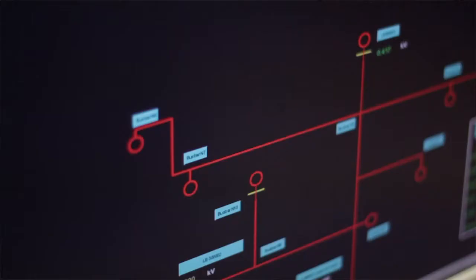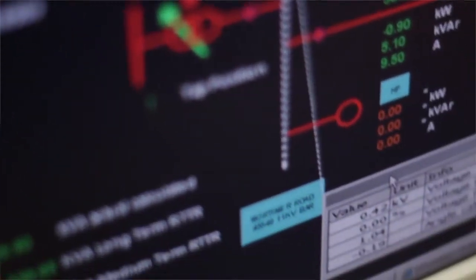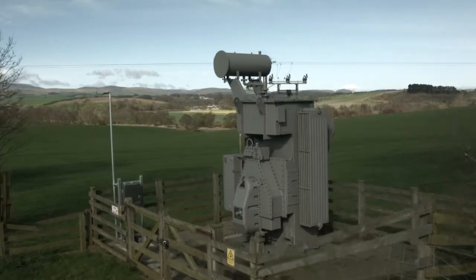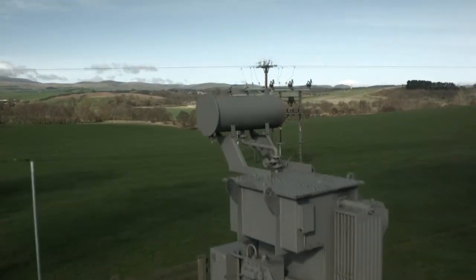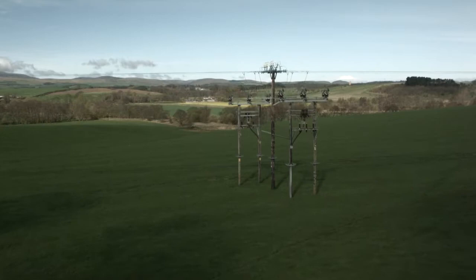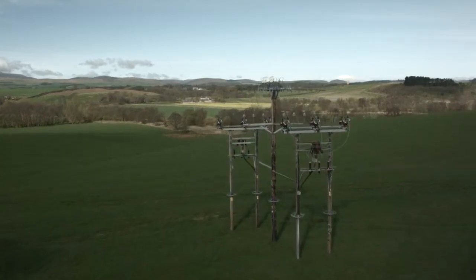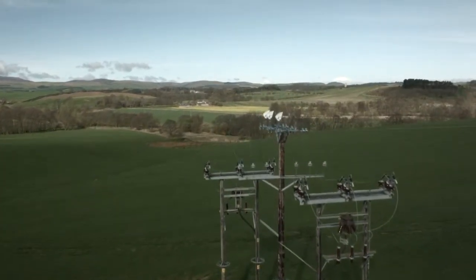What Gus gives us is visibility right across the network. We've deliberately built it to take a view right down to where customers are, right across the low voltage network, to see what the voltages are on that part of the network, and use that to control the tap changes, whether at the secondary or even at the primary.